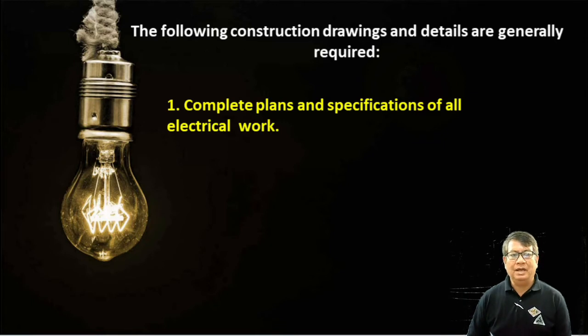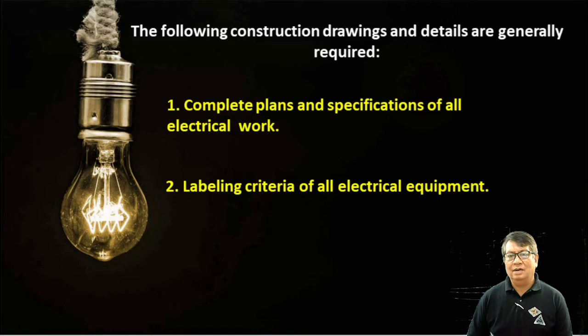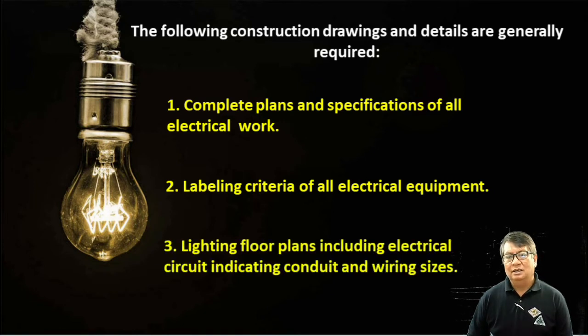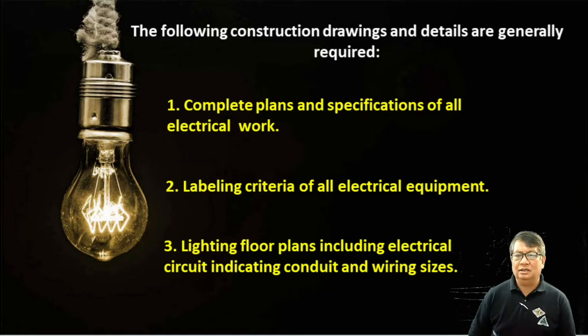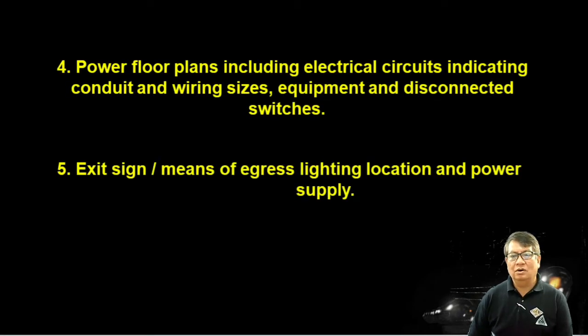Unang-una, complete plans and specifications of all electrical works. Pangalawa, we have labeling criteria of all electrical equipment. Then next, lighting floor plans including electrical circuits indicating conduit and wire sizes. Okay, so floor plan, kailangan po natin ito, which will include the electrical circuit, which indicates conduit or any tubing or raceways and others, to protect the insulation of our wire, and it also includes wire sizes. Okay, so the fourth one, power floor plans including electrical circuits indicating conduit and wiring sizes, equipment and disconnect switches.